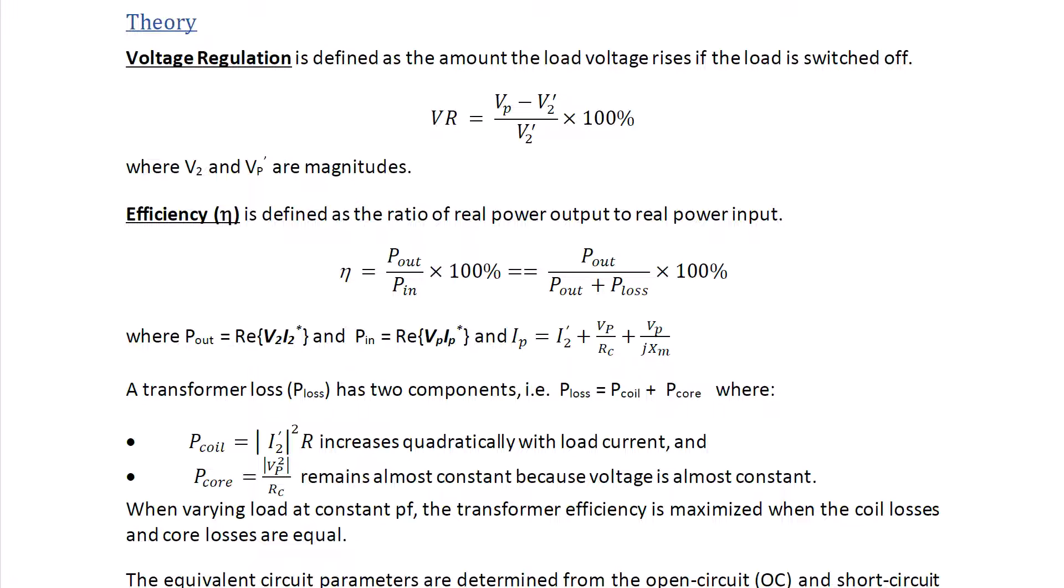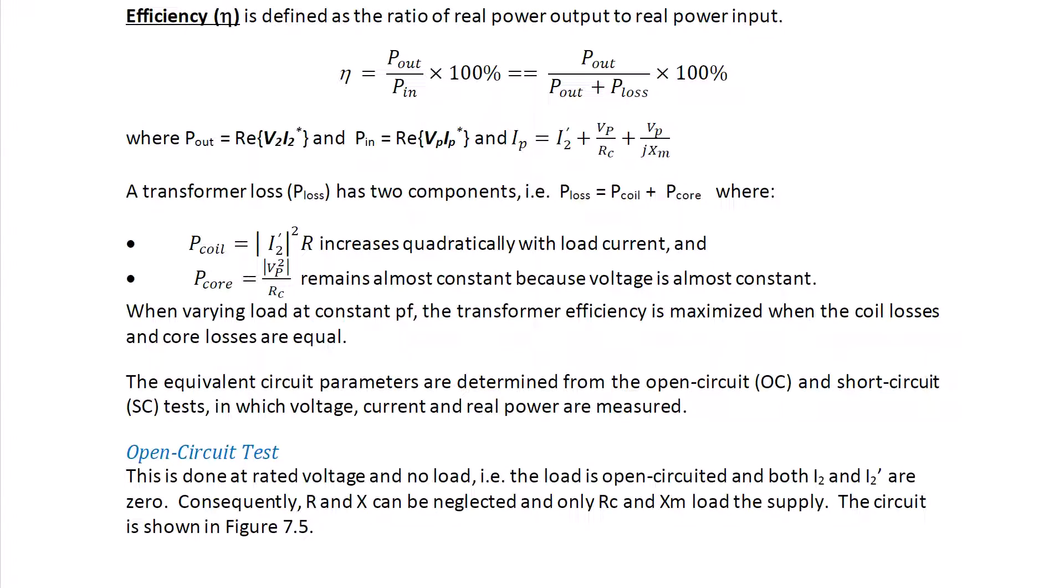Note that we saw in the previous lecture that ideally you'd want voltage regulation to be 5% or lower, and that by increasing the power factor, you can reduce the voltage regulation and increase the efficiency. The equivalent circuit parameters are determined from the open circuit and short circuit tests in which voltage, current, and real power are measured.